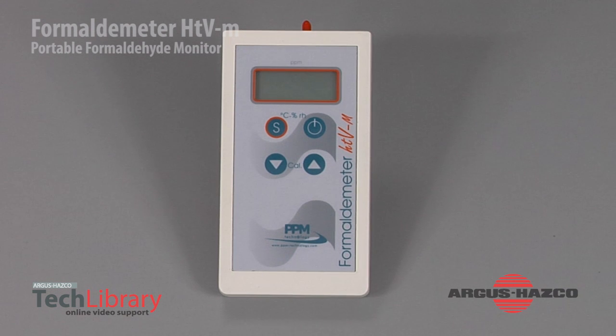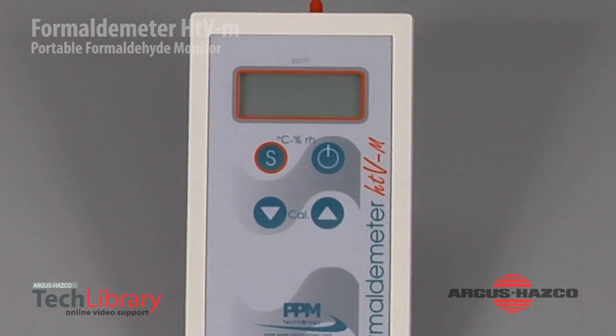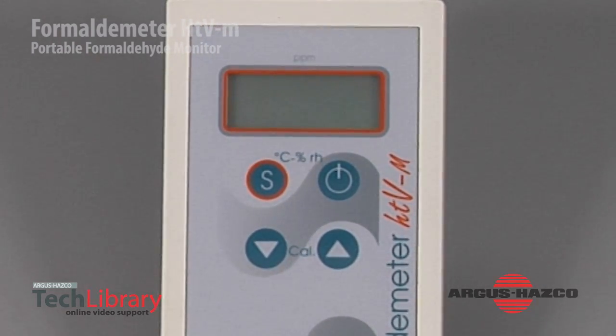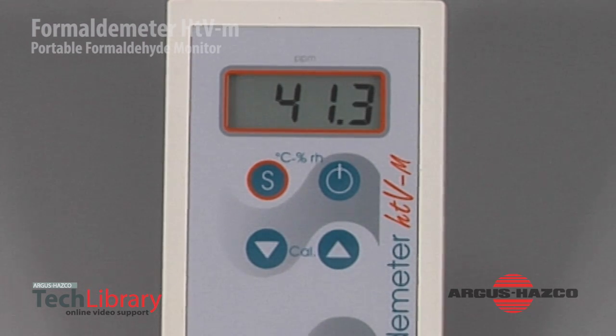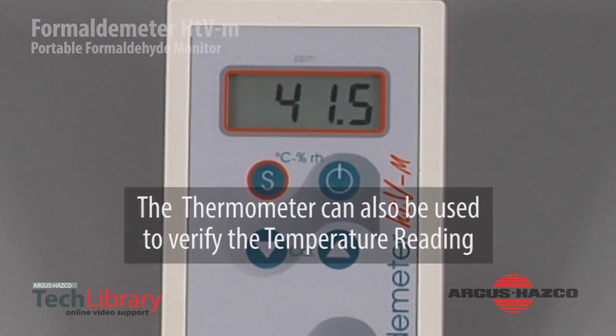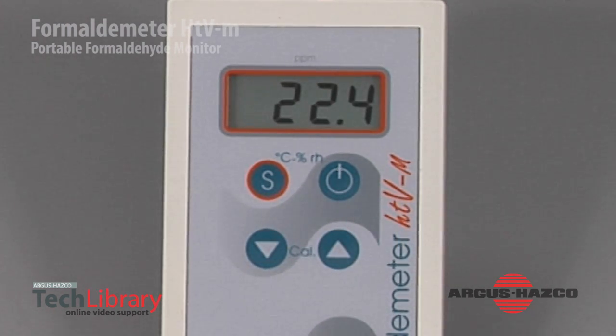I'll take you through the steps in properly using your instrument step by step, first showing you the 2 buttons to push to make sure we know what the temperature is in the environment we're monitoring in, and also the relative humidity. We need those criteria to calibrate the instrument. To do so, we push the S button, which is the sample button, and the power button. The screen will light up and indicate to you what the temperature is, as well as the relative humidity in the room. As you look at the screen, you'll see 22.4 as being the temperature in Celsius and 39.3 being the relative humidity.